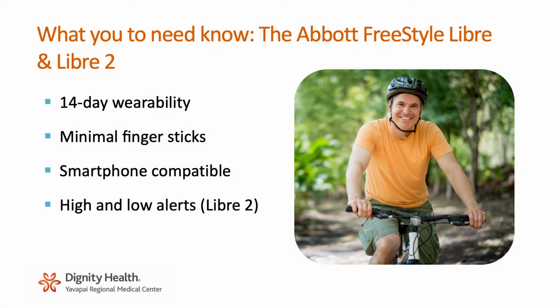So the first one out on the market is the FreeStyle Libre made by Abbott, and it has a FreeStyle Libre 14-day and a FreeStyle Libre 2. They are both worn for 14 days. There's minimal finger sticks with them. They are both smartphone compatible, so that means you don't have to carry an extra device. You can use your smartphone to scan the sensor and get your glucose values. The Libre 2 has high alerts and low alerts, so you can personalize your alerts. So if you want to be notified when your blood sugar is at 70, it can notify you that you're going low. Or if you want to be notified when it's high, you can set that alert also. So you can have both a high and a low alert with those.